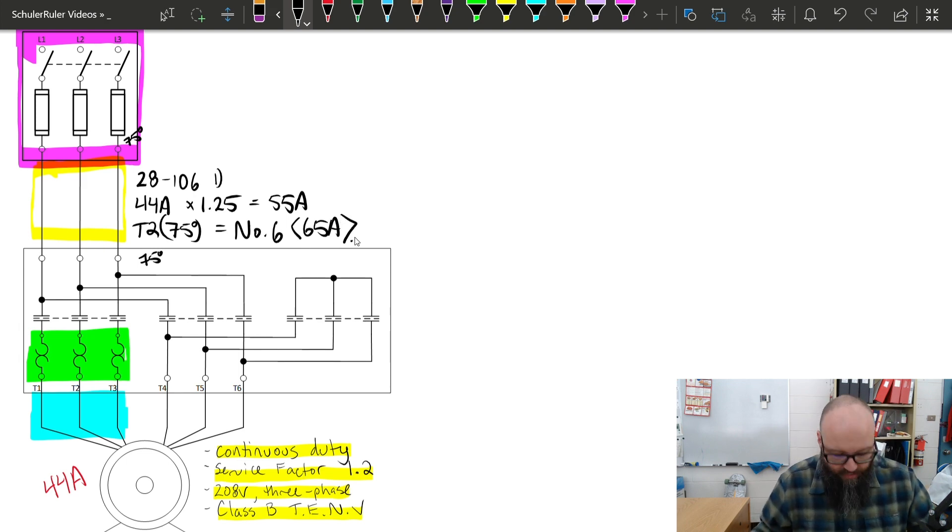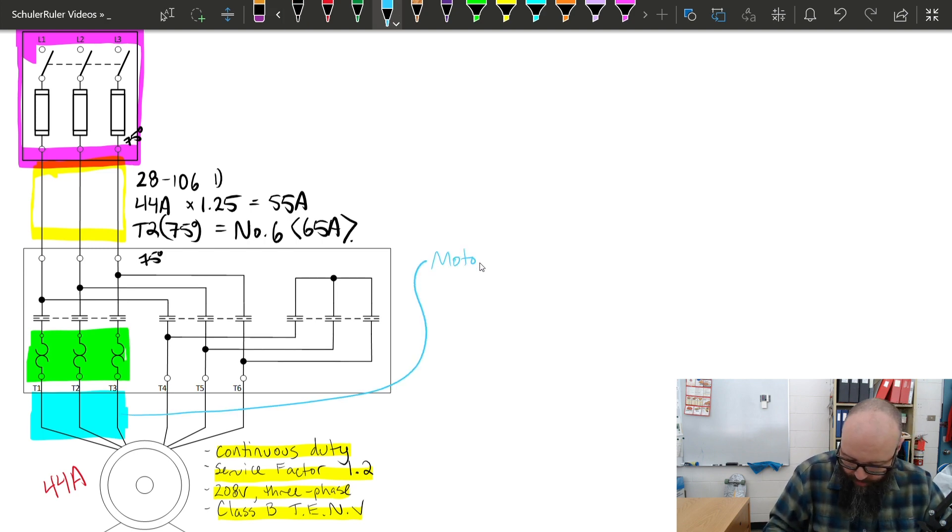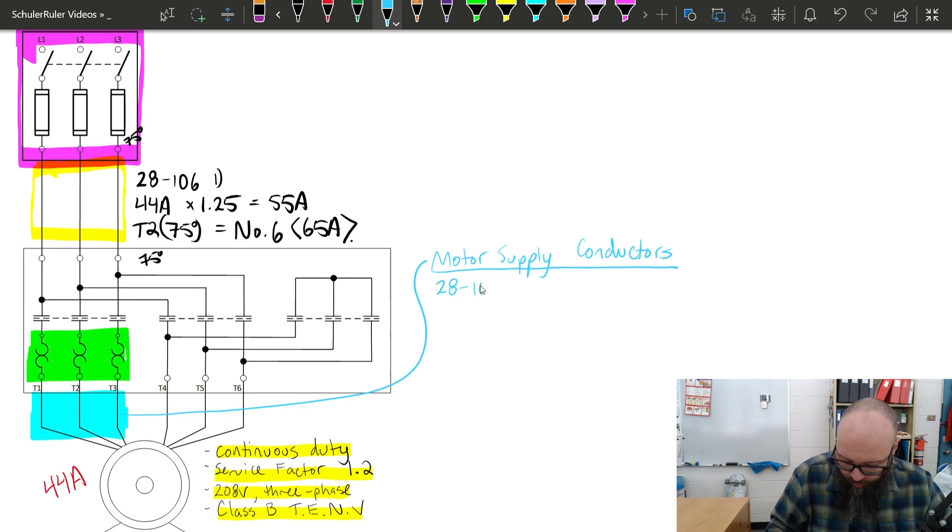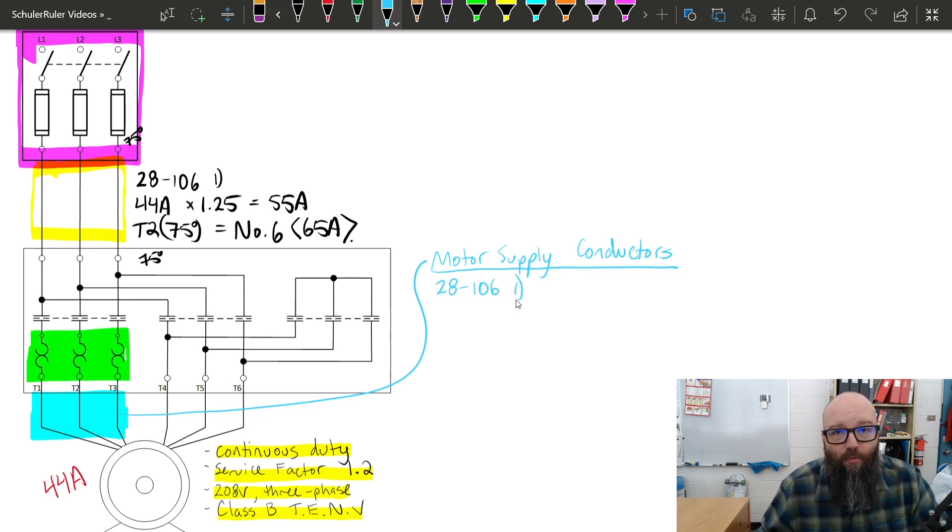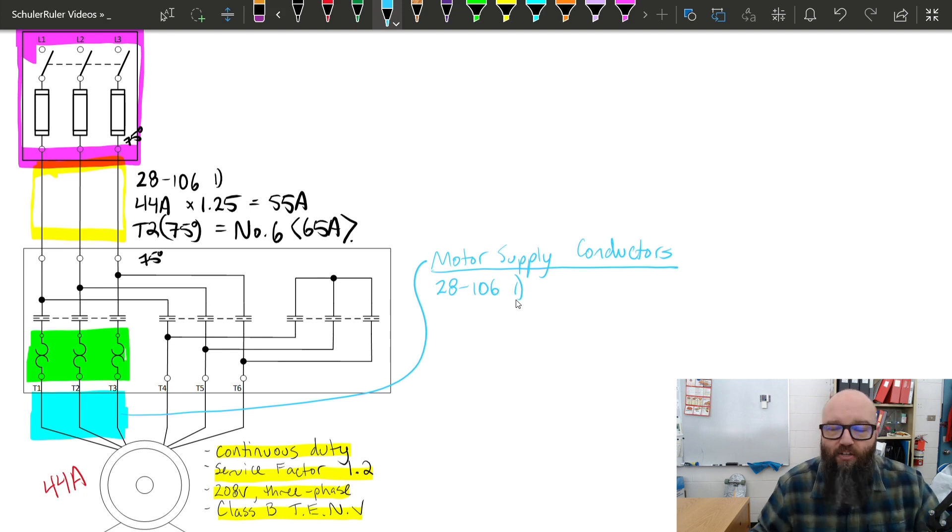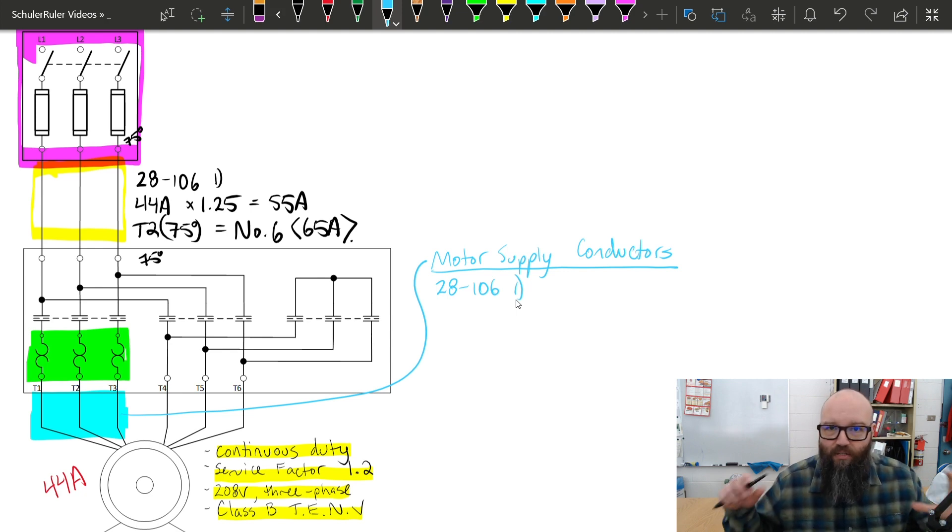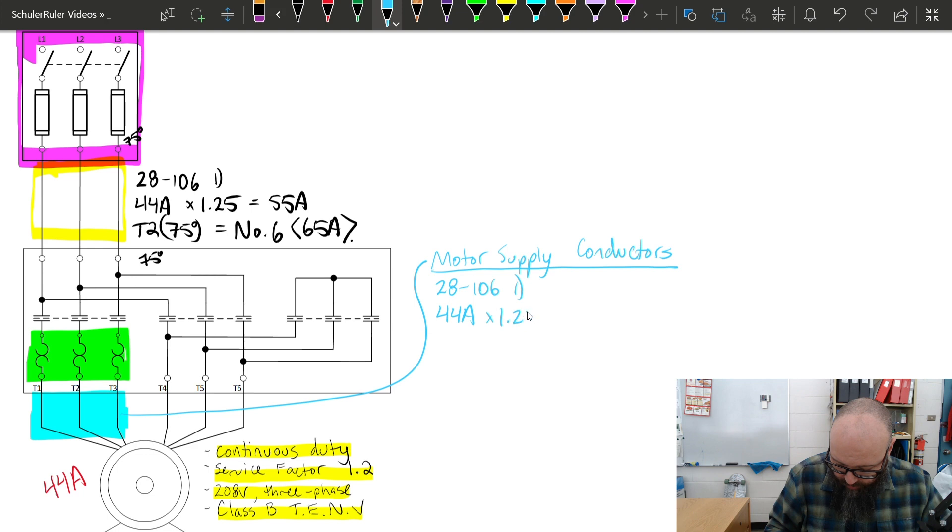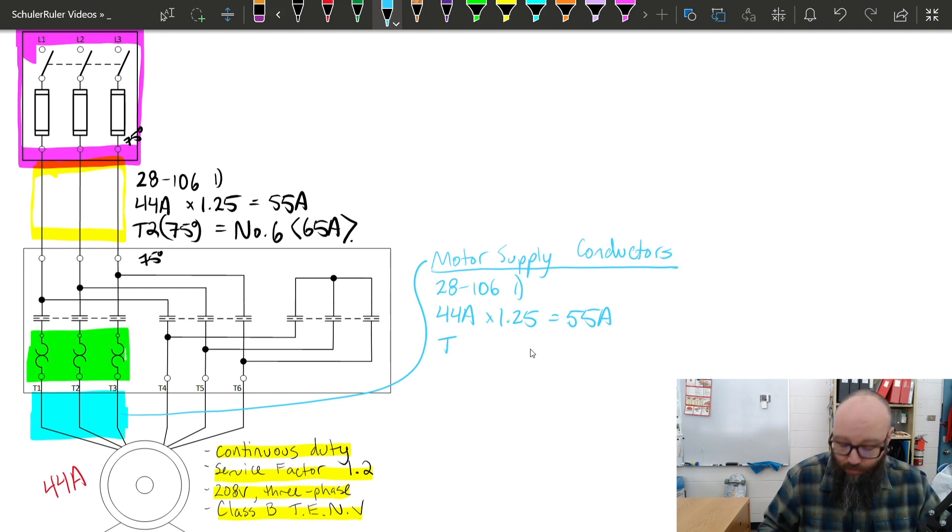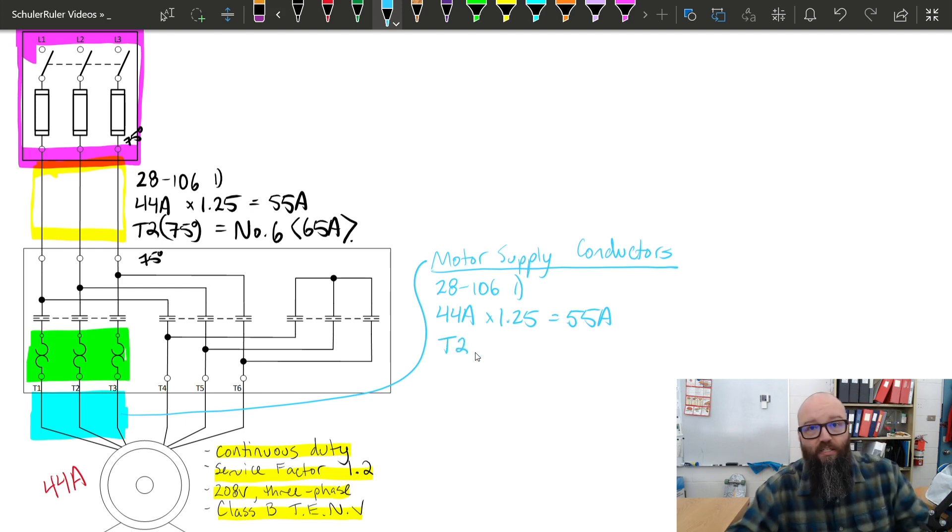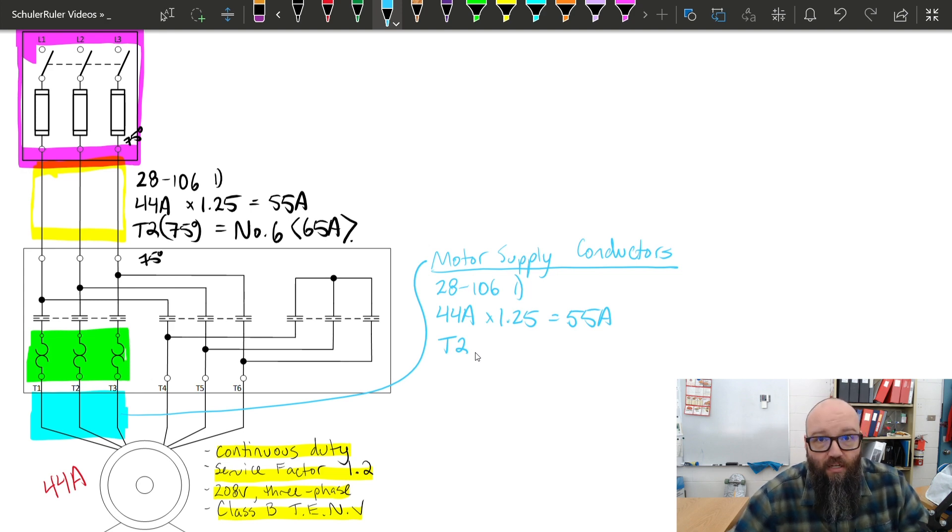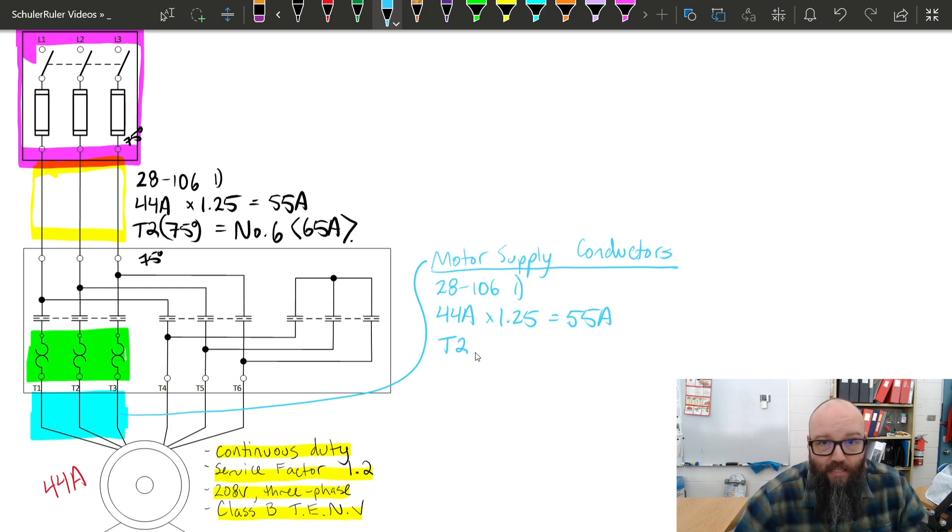Next thing we're going to go for is that motor supply conductor. We are still going to use 28-106, subrule 1, to determine that minimum ampacity. It's the same calculation as your branch circuit conductors, but it's good just to make sure we separate these two conductors. So, we're going to go again, 44 amps times 1.25 gives me the same 55 amp minimum ampacity. Table 2, now, this is important. This is the differentiation between the motor supply conductor and the branch circuits. Because we have a motor supply circuit here that is anything other than a class A with 90 degree insulation, we have a class B here, I'm required to use the 75 degree column when selecting the size of my conductor based off the 75 degree column ampacity.